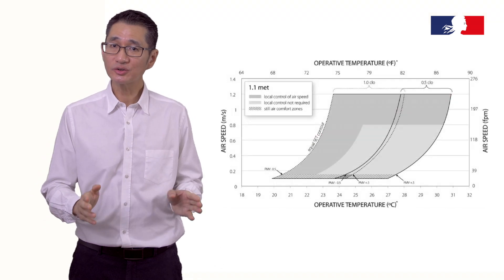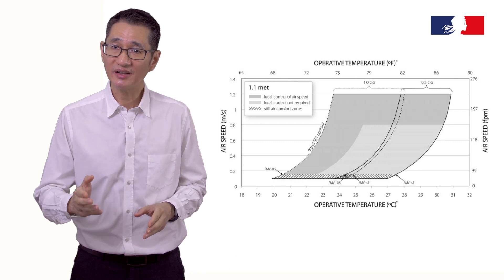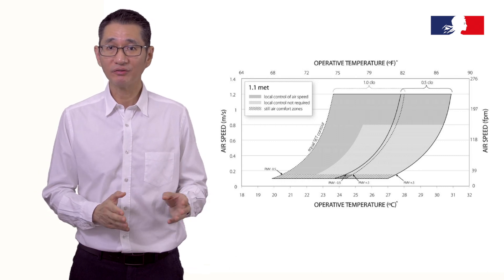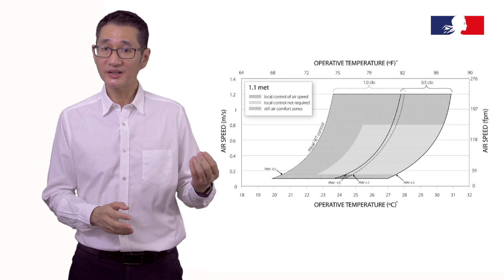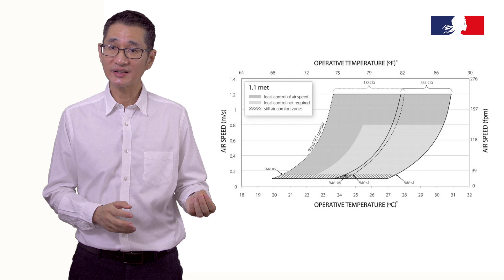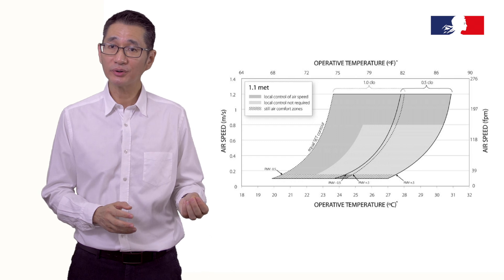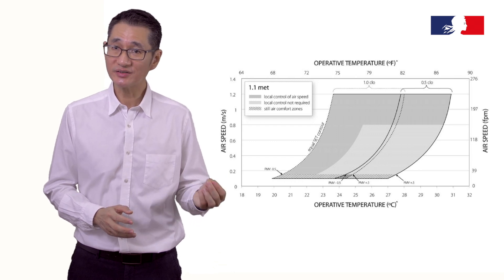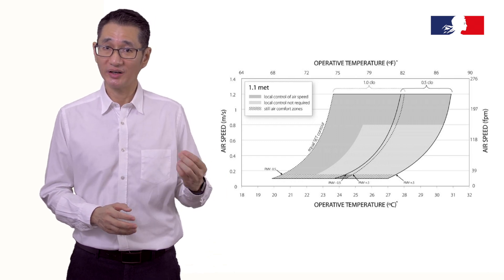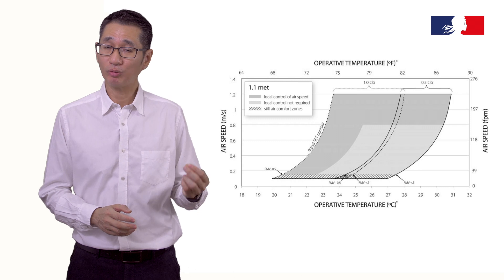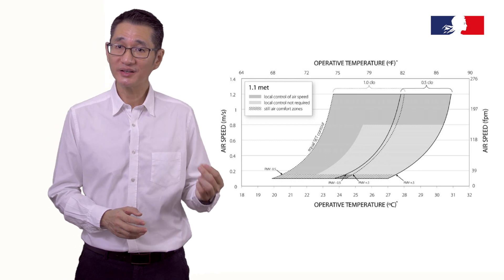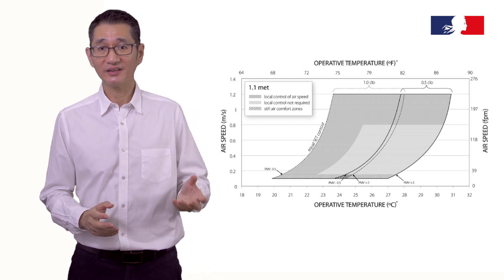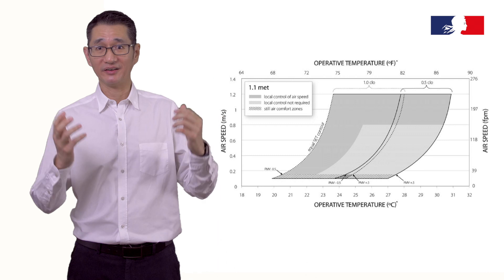The last tool to be introduced is elevated air speed for thermal comfort. This tool indicates that it is possible to feel comfortable up to 30 degrees Celsius with an air speed of 1.2 meters per second — that is, sitting underneath a ceiling fan.